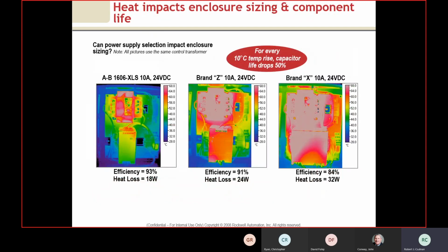Here's something that I think is really key. If you look at a couple of different power supplies here, we utilize the heat indication here. You'll notice that on a low or inexpensive power supply the efficiency is at 84%. Heat loss is 32 watts. You see a lot of heat. And again, these are like little hair dryers running inside the unit, just pumping heat into the panel. This unit here is a little bit more efficient, 91%, but it still has heat loss. If you look at the higher efficiency unit, the efficiency is at 93% and the heat loss is at 18 watts. So you get a huge difference in the way this is set up.